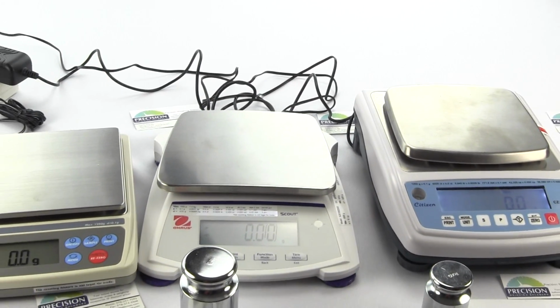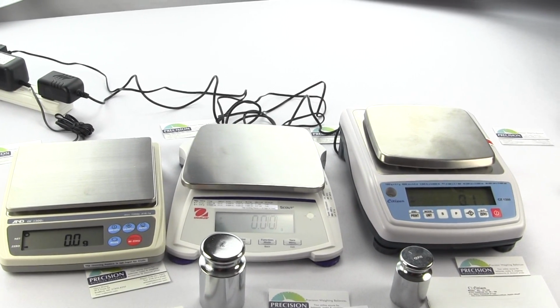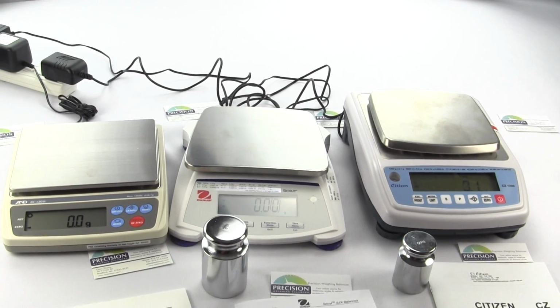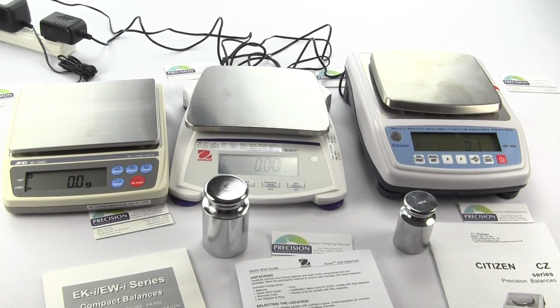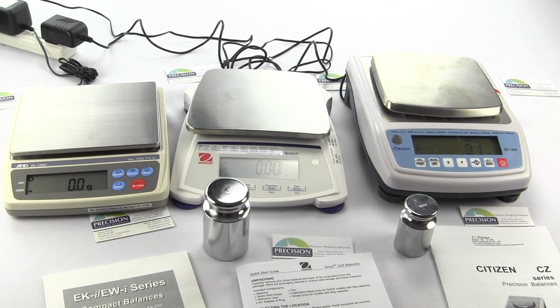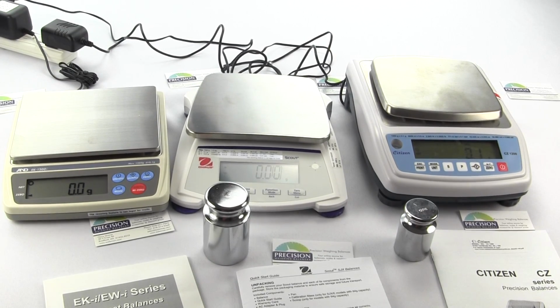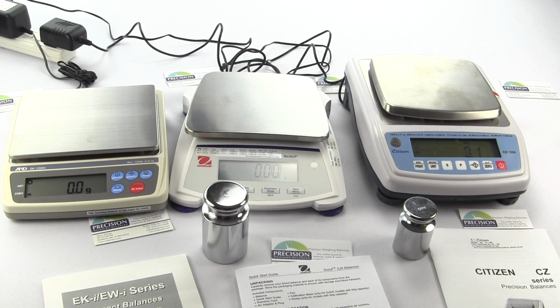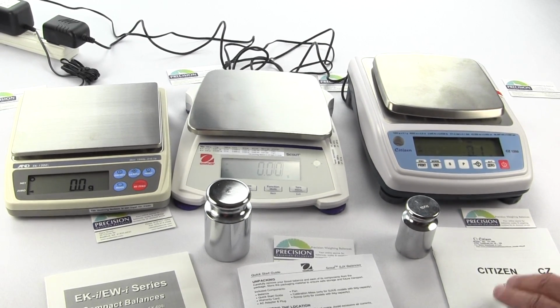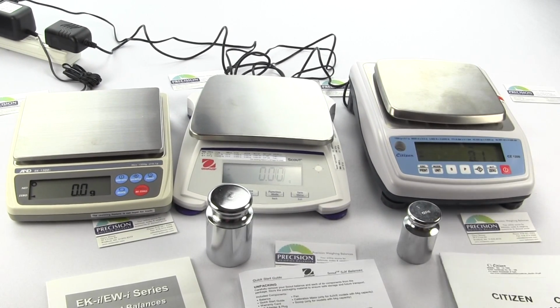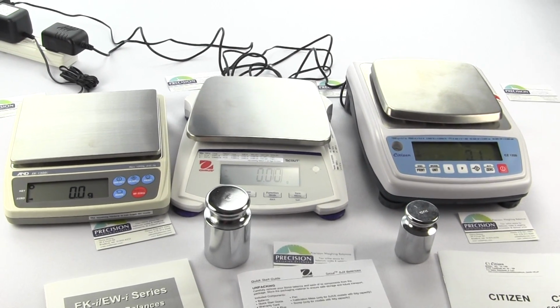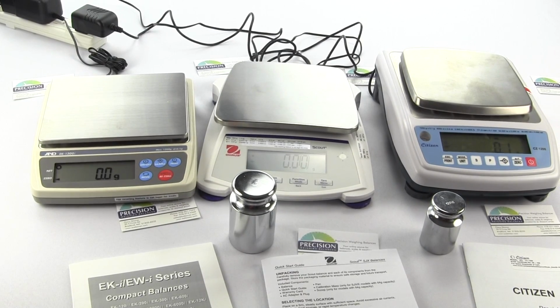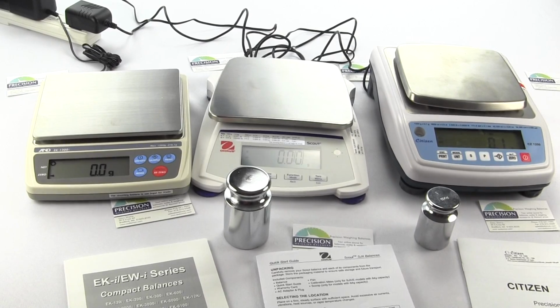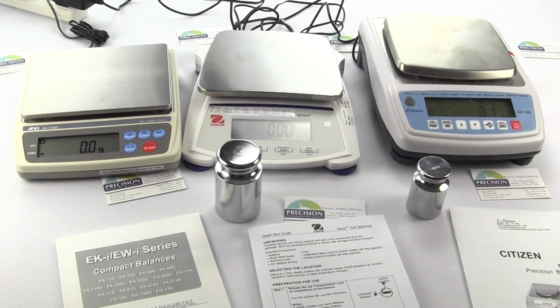And then on the Citizen, there's nothing here at all to lock out. But if you download the Certificate of Conformance, the CoC on this scale, the CoC number is 09-109. It states that the device is sealed with a Category 1 audit trail. Access to the audit trail information is by pressing the on-off key during self-calibration, pressing the P button, and it will show the number of calibrations. So the manual doesn't even state it, and that's why I say again the manual is pretty weak. But that's how they would seal that unit. So that really covers the majority of the differences. There are some more. I'd recommend you download the user manual, you know, to give you an idea.